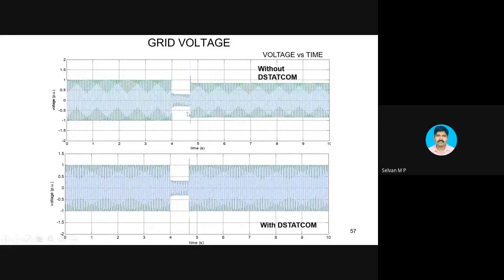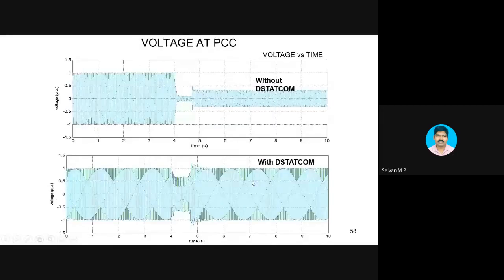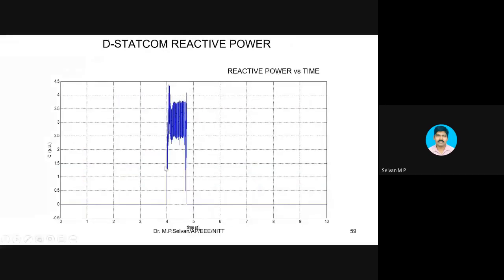So this, you can see the grid voltage without the STATCOM and with STATCOM. Without STATCOM, the grid voltage is not coming back to the original value, but with the STATCOM, the grid voltage comes back to the original value after clearing the fault. And similarly at PCC also. And this much amount of reactive power is injected by the STATCOM during the grid fault. When the fault is present, this much reactive power is supplied by the STATCOM.